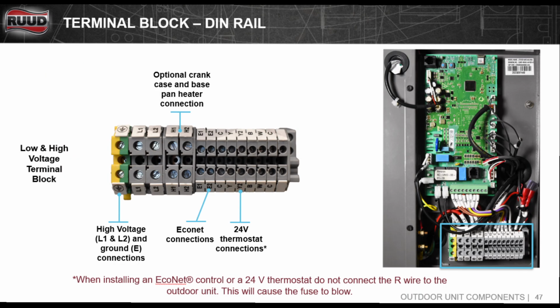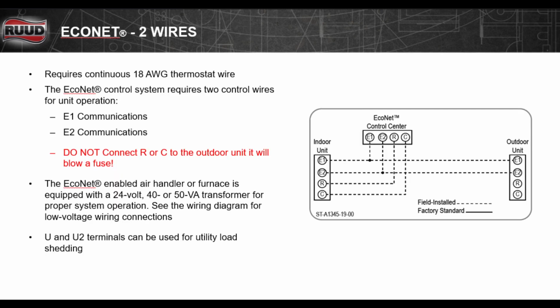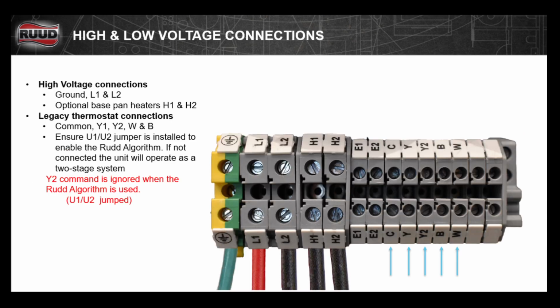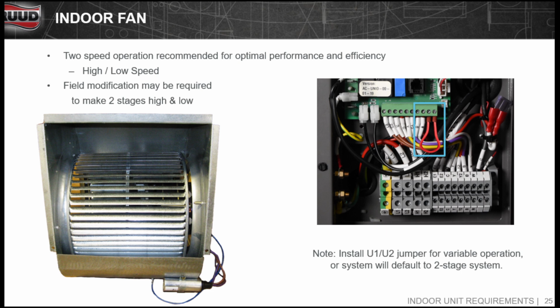Once inside, you will locate the DIN rail, which you will be using to make all your connections. If wiring this with an EcoNet controller, you are not using the R and the C, or you will blow the fuse. You will only be using the E1 and E2 connections. Legacy thermostat connections will be utilizing common Y1, Y2, W, and B. It's recommended to jumper the U1 and U2, and that will activate the Ruud algorithm, which ignores the Y2 command.